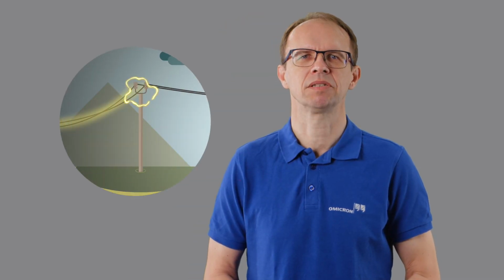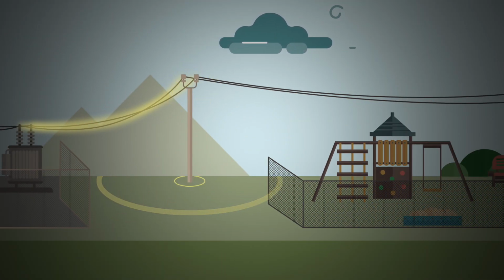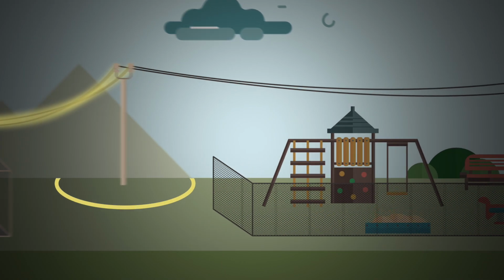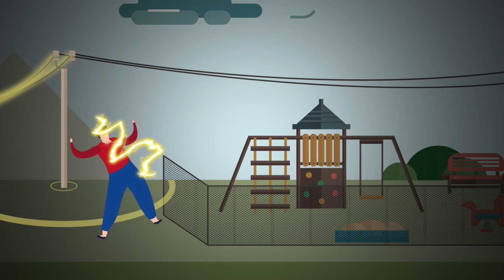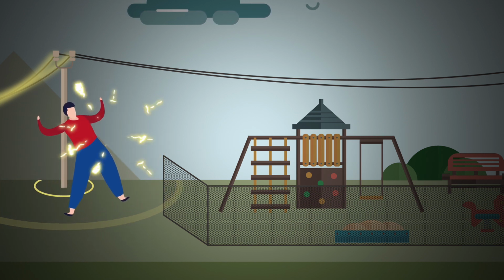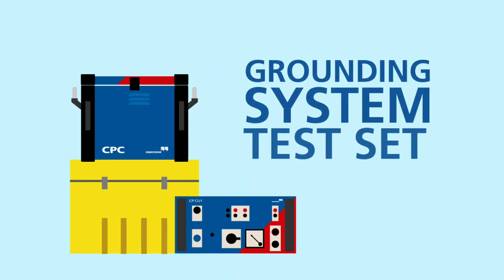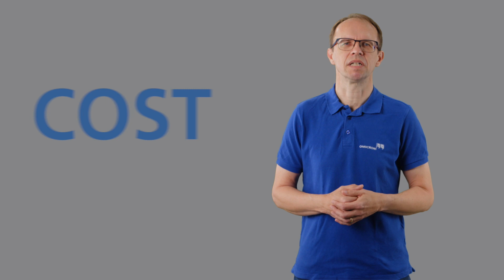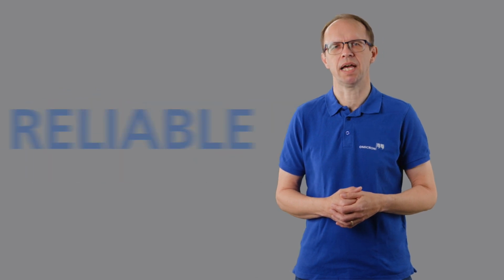In the event of ground fault, dangerous step and touch voltages can occur inside and outside a substation. An effective grounding system is crucial to ensure people's safety. Our CPC 100, in combination with the coupling unit CPCU1, is the ideal solution to verify the condition of your grounding system. The measurements are cost-effective, fast and reliable.